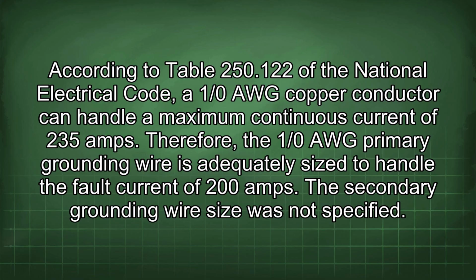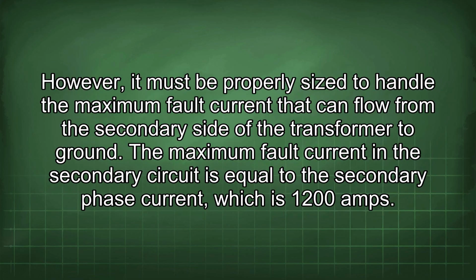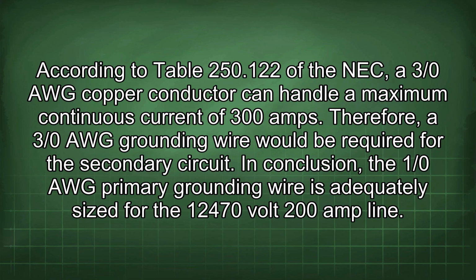The secondary grounding wire size was not specified. However, it must be properly sized to handle the maximum fault current that can flow from the secondary side of the transformer to ground. The maximum fault current in the secondary circuit is equal to the secondary phase current, which is 1200 amps. According to Table 250.122 of the NEC, a 3/0 AWG copper conductor can handle a maximum continuous current of 300 amps. Therefore, a 3/0 AWG grounding wire would be required for the secondary circuit.